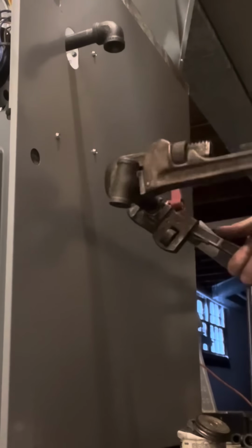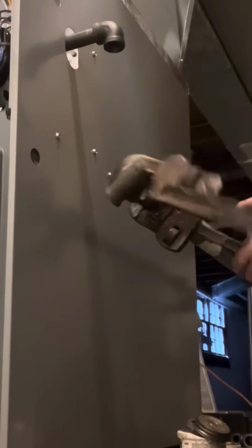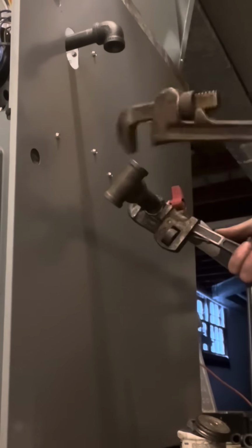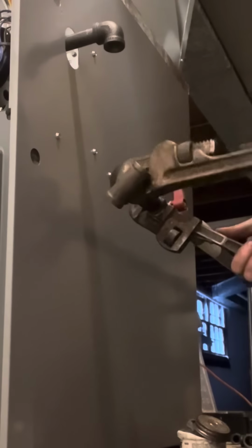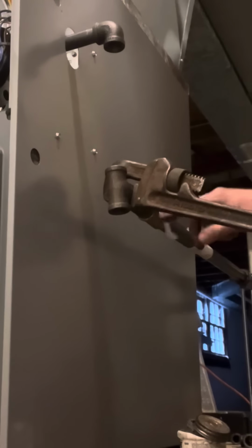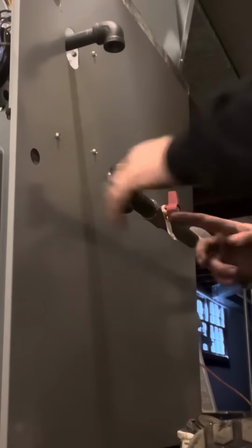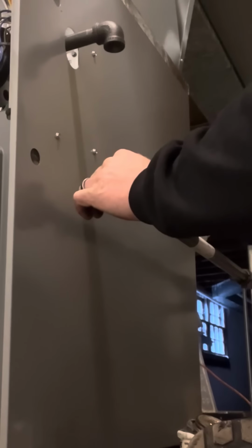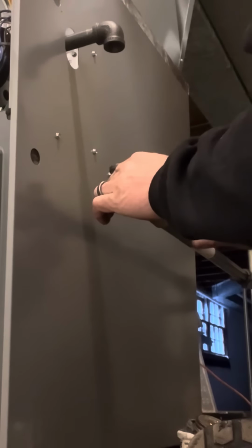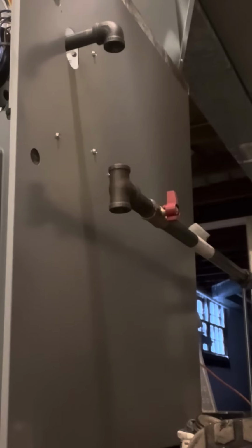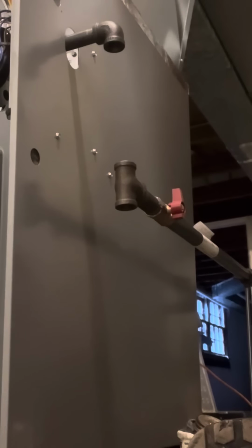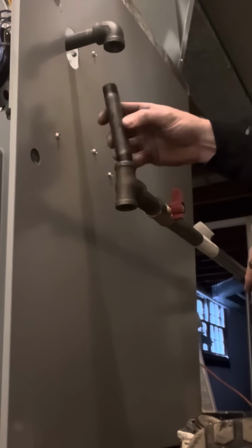But I want to talk about the actual code for a second, because I feel like a lot of people don't actually know the codes that are associated with where I live. So the first part of the code dictates the location of a sediment trap. A sediment trap is installed on any appliance that is not manually operated. So you think furnace, water heater, boiler, stuff like that. Things that are going to run without your help. You don't need it for an oven, you don't need it for a dryer, not by code at least.